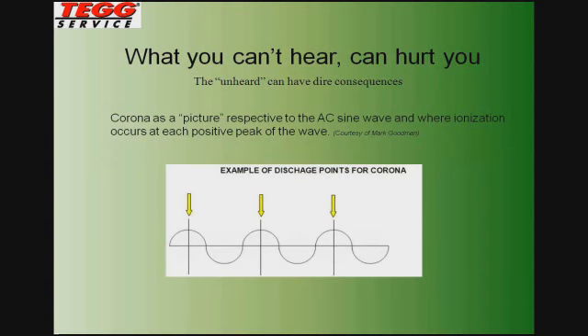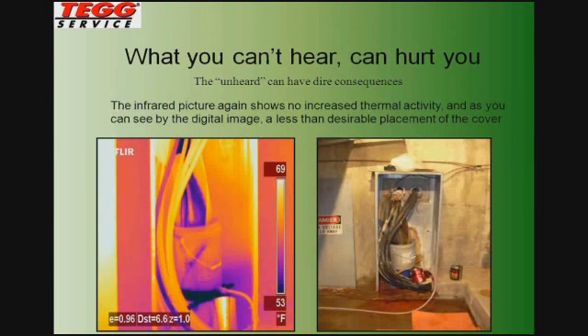Looking at it from the sine wave, when corona occurs, nuisance corona, the ionization takes place at the peak of the positive half cycle, which is why you are going to see a lot of symmetry here, or timing, if you will, every 16 milliseconds. That gives us the rich 60 hertz fault frequencies and noise content, as well as the symmetry in the time domain when the excursions occur. It's a very uniform event, and it's easy to pick out if you know what you are looking for. Corona can be confused with some other issues that I'll talk about in a moment.